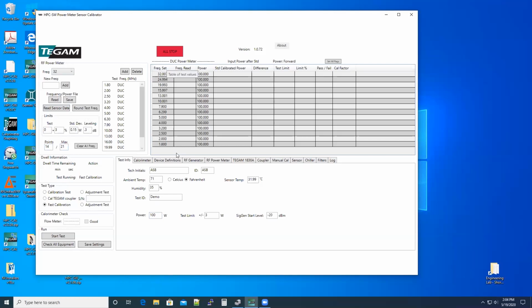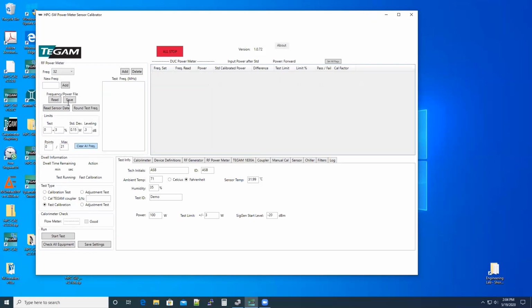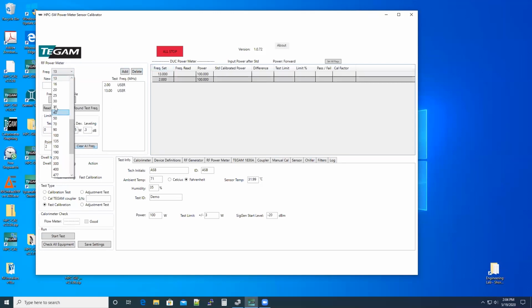Now it takes several minutes to test each of these points. So what I'm going to do is clear this list and then just type back in 3 of them for the sake of illustration. So I'll pick a low one, a medium one, and a high one. We can pick frequencies by pulling down the list of predefined frequencies. And we'll just add, let's say, 2 and 13 and maybe 25 megahertz.